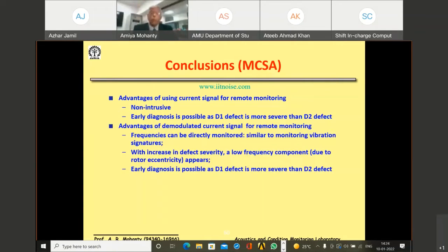And again, on the ground, MCSA can be used because there is a current carrying conductor going from your control room to the motor which is driving the fans, blowers, whatever it may be. Now, again, let me tell you, today the technology is such. We just had a discussion on wireless data acquisition. Imagine if I have a Hall effect sensor or a current transformer with a Wi-Fi transmitter. Today, there is a foundry in Hyderabad where they are monitoring all their operations, not through vibration, just by remotely measuring the current at all locations.